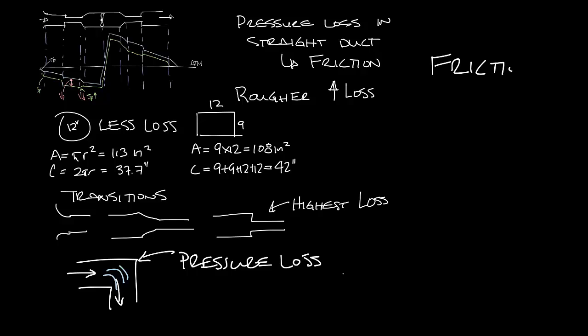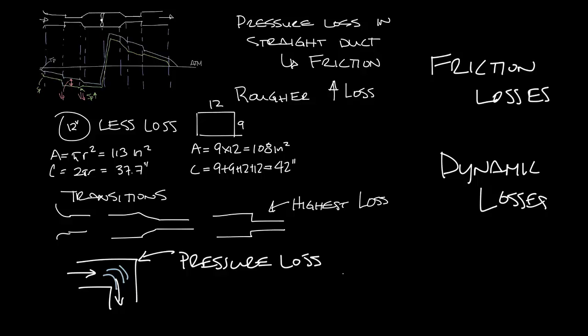These pressure losses fall into two categories. Frictional losses caused by air moving through the ductwork and dynamic losses caused by disturbances of the airflow from changes in direction or area. So these top ones would be friction losses and the bottom ones would be dynamic losses.